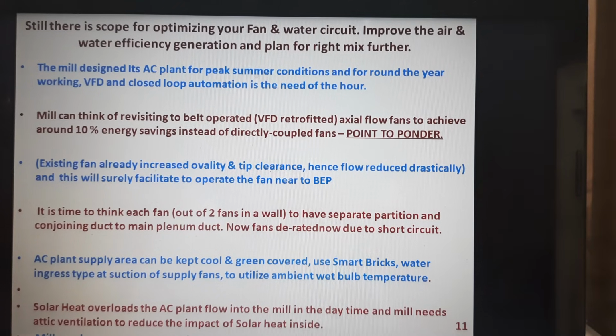The VFD has to function in closed loop automation for the given mill for the given time, either in the peak summer month, the winter month, or the lean months. The VFD needs to be mandatorily closed loop operated instead of manually operating the hertz of the VFD.